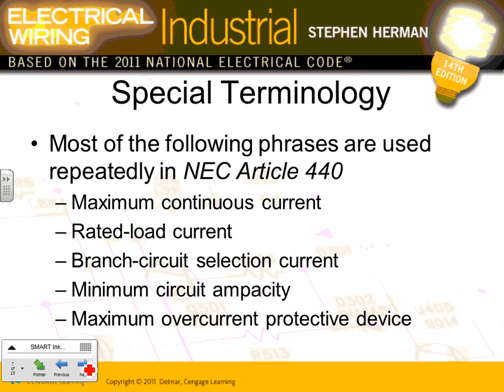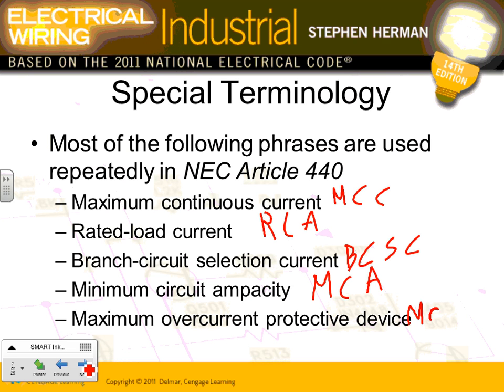Every time you have some type of compressor in a building, there are these terminologies. We touched on these before, so they shouldn't be new to you. We have maximum continuous current. We have rated load amps. We have branch circuit selection current, we have minimum circuit ampacity, and we have maximum overcurrent protection device. These are very important.